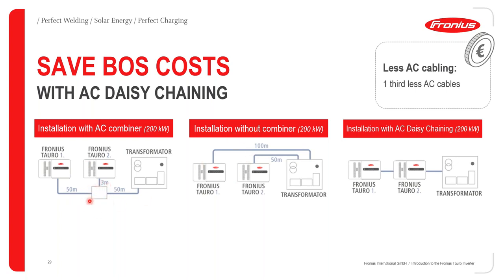But then again, we are also incurring the cost of the AC combiner box here. With the Fronius Tauro AC daisy chaining, you're able to achieve a much shorter cable distance, because if you assume that we have the same distance from the farthest inverter to the transformer of about 100 meters, then we are still able to cover that entire 100 meters by daisy chaining the first inverter to the second one, and then from the second inverter going directly to the transformer. And therefore, in this case, at the transformer we require only one AC disconnector.